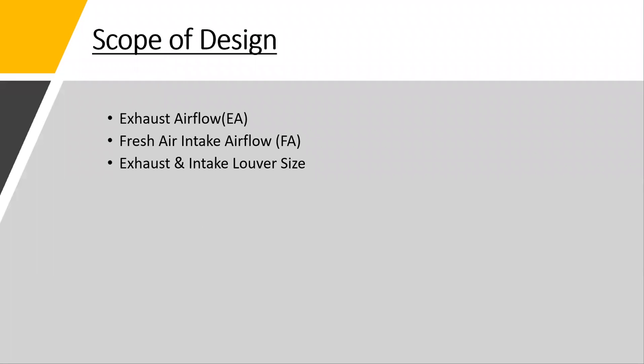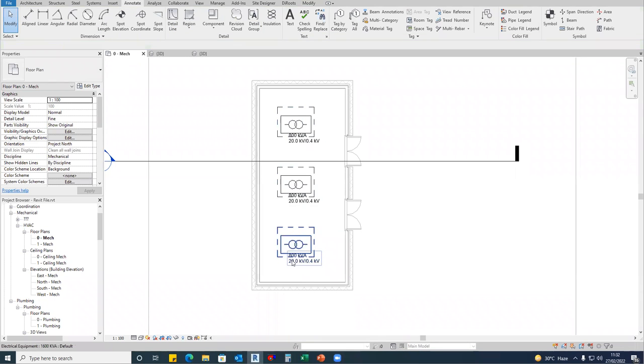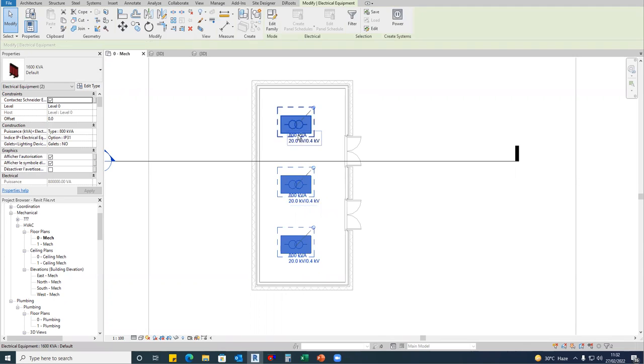So in this, what is the scope of design? First, we need to calculate the exhaust airflows, fresh air intake airflows, and then the louver size. So in the drawing, we have these three transformers. Okay, so when you select it, you can change the ratings. Okay, we have 250, 400, 630 kVA, 800 kVA, up to around 3150 kVA. So let's, for example, I have taken 800 kVA transformers each.